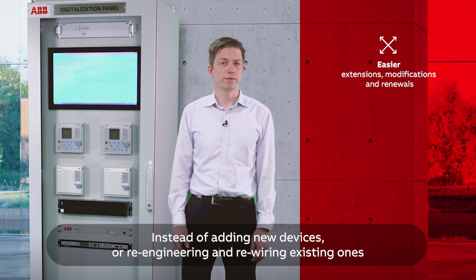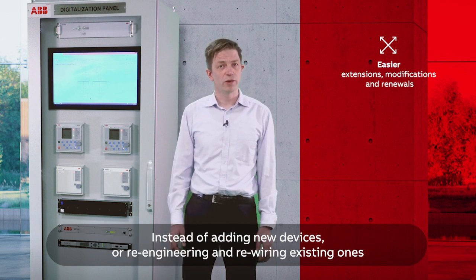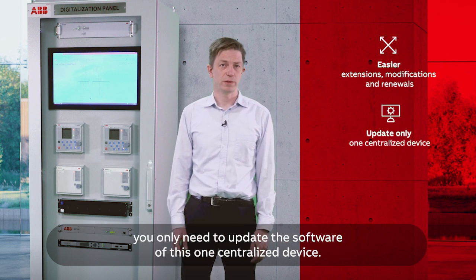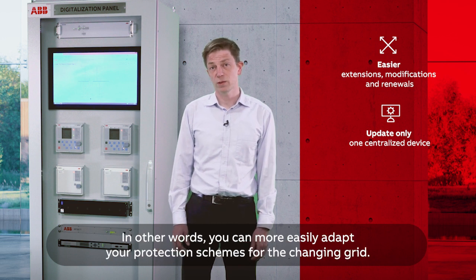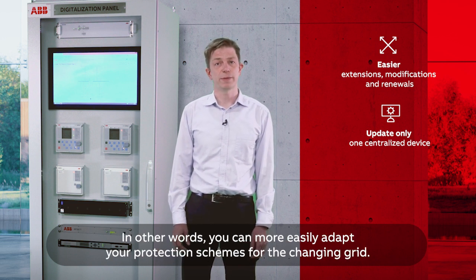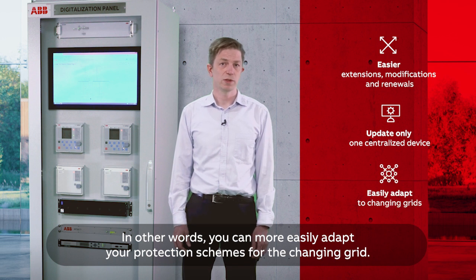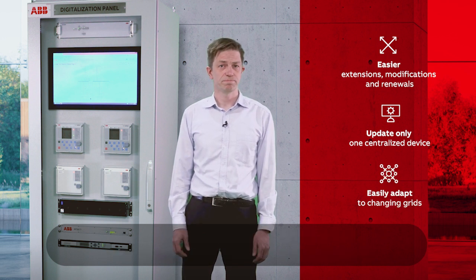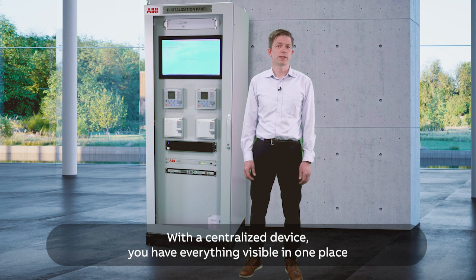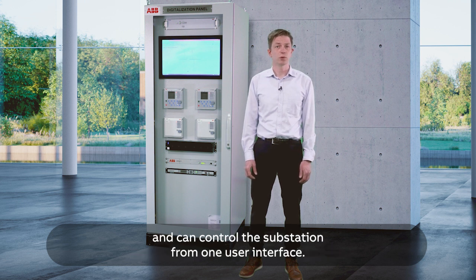Instead of adding new devices or re-engineering or rewiring existing ones, you only need to update the software of this one centralized device. In other words, you can more easily adapt your protection schemes for the changing grid. With a centralized device, you have everything visible in one place and can control the substation from one user interface.